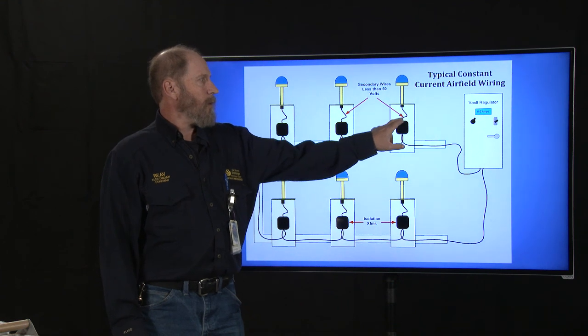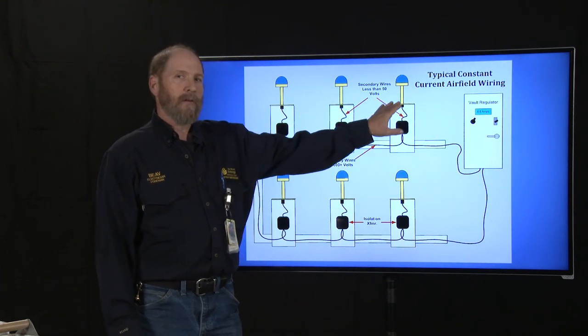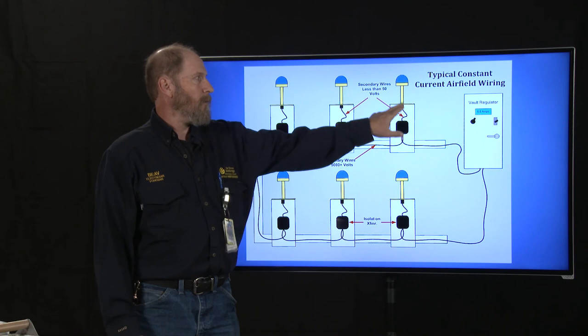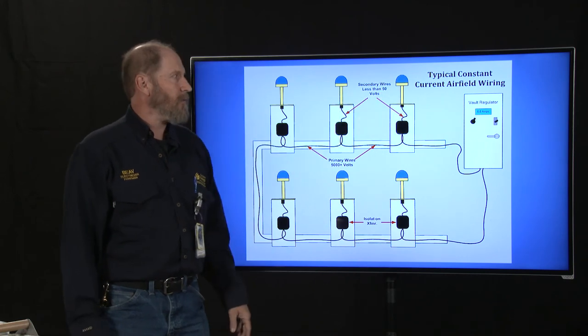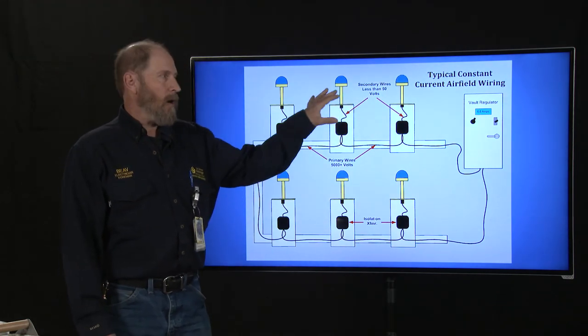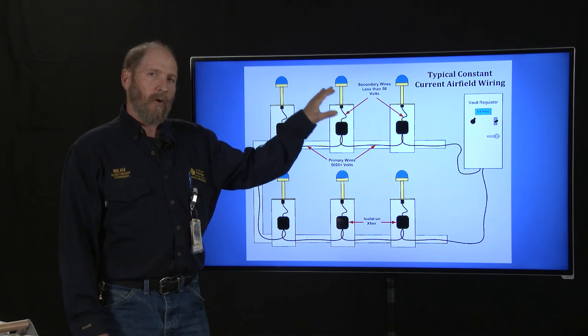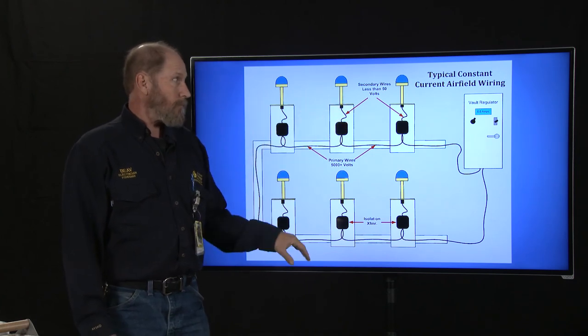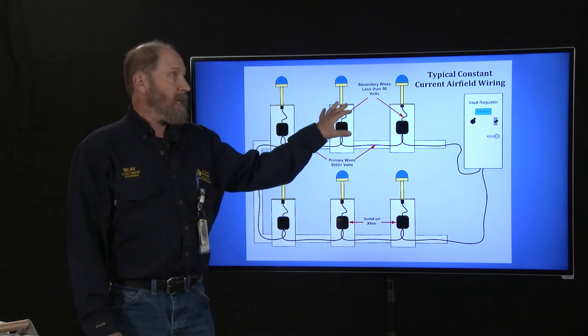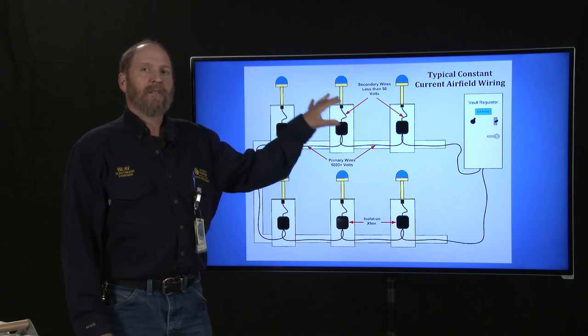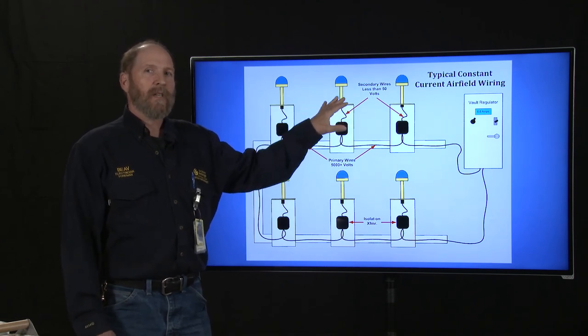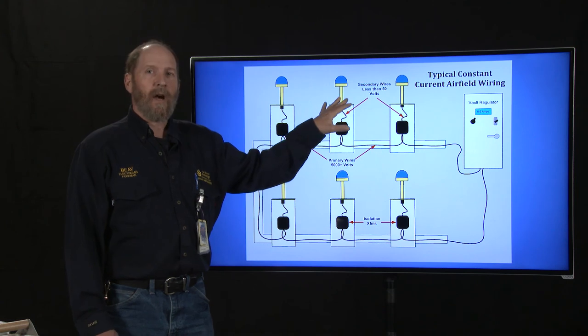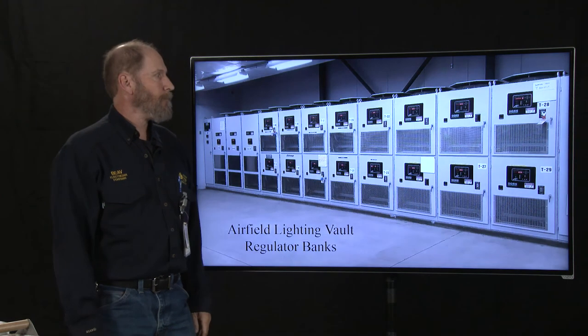Okay, on our secondary side of the transformer, the wires go up to feed our lights. This is low voltage wiring. It steps it down to less than 50 volts. So our lighting on an airfield is actually low voltage wiring. And these are low voltage lights. But to think of this as a low voltage system is extremely dangerous. And I think you'll understand why after a few slides here.